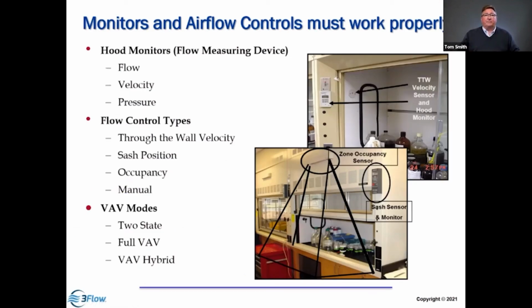When we look at the airflow control mechanisms, whether it's flow that's being measured or velocity or pressure, every hood should have a hood monitor. How else are we going to tell the operator that the hood's got adequate flow? And it needs to be calibrated using our techniques. And then if we look at what's modulating flow, a through-the-wall velocity sensor has a sensor in the sidewall of the hood, and it's measuring that velocity and reporting the value on the sensor. A sash position sensor is looking at the height or the width of the sash opening, and it's calculating the area and then trying to control to a constant velocity. Then you have occupancy-based. If you have an occupancy sensor, if there's no one there, it's at a lower flow. If somebody steps into the zone, it increases flow. Who makes sure that works properly?